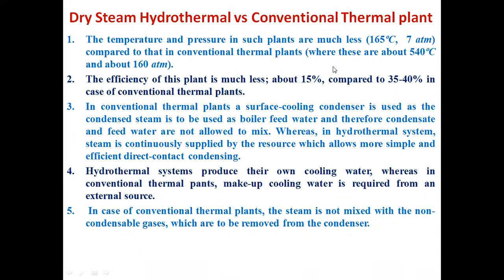The first difference is that the temperature and pressure in dry steam hydrothermal power plants are much less. As we saw earlier, it is just about 165 degrees centigrade and 7 atm, the parameters of steam supplied for electricity generation. Whereas in a conventional thermal power plant, steam having a temperature of the order of 540 degrees centigrade and a very high pressure of 160 atm is utilized for extracting energy. So this is the first difference between the dry steam hydrothermal system and the conventional thermal power plant.